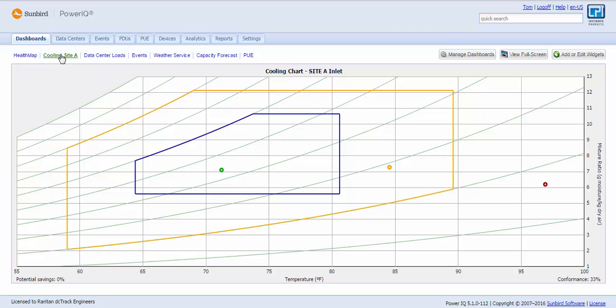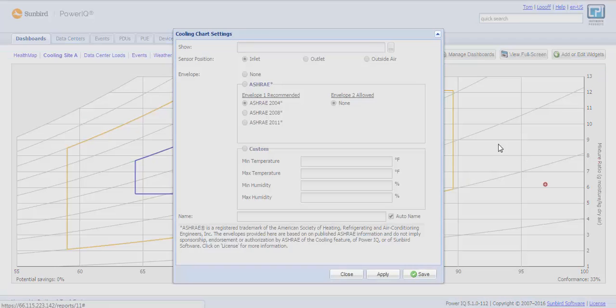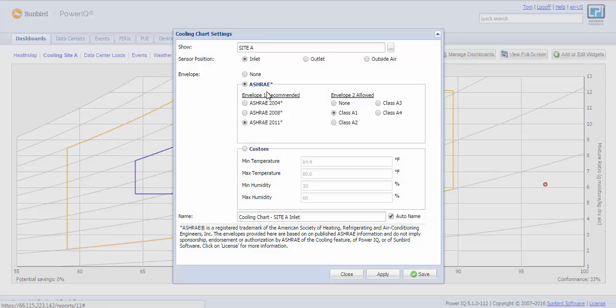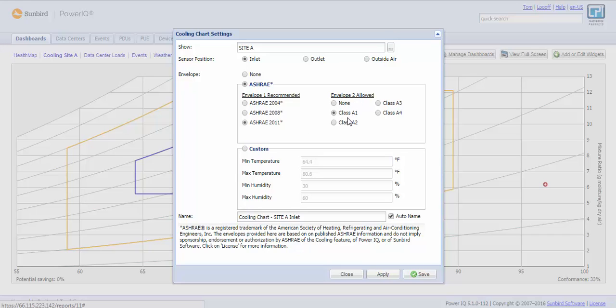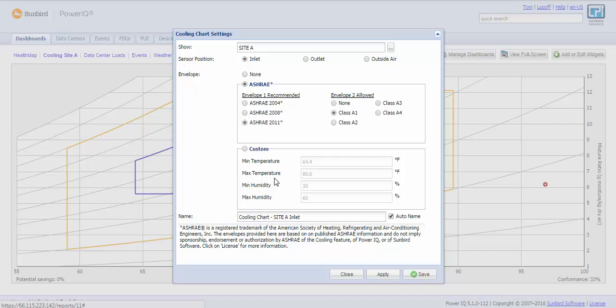A very popular dashboard widget is our cooling chart, which provides a number of ASHRAE ranges that you can measure your sensors against. In this particular case, I'm going against ASHRAE 2011, and I'm selecting an allowed envelope of class A1 equipment. So I'm saying that my equipment in my data center is at least A1 type, and therefore I'm measuring the temperature from the inlet of the cold aisle and comparing that to the recommended and the allowable ranges. I also have the ability to set my own custom range if I want to measure myself against HP, IBM, Dell, or my own standards.